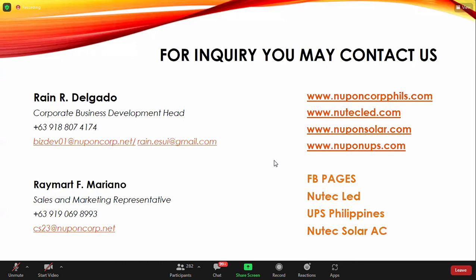Sir Stewart, from Joel Elige: if the solar power or DC power is not available, will the working voltage of the unit go back to AC voltage or still remain DC due to the hybrid system? The unit will run on DC, but it will work on the 240 volt or 220 volt system. There is an inverter inside the unit which will convert the power. From John Celestino Canama: is the AC-DC aircon manually or automatically switched to the solar or grid source? Yes, it'll automatically switch. You don't have to do anything.